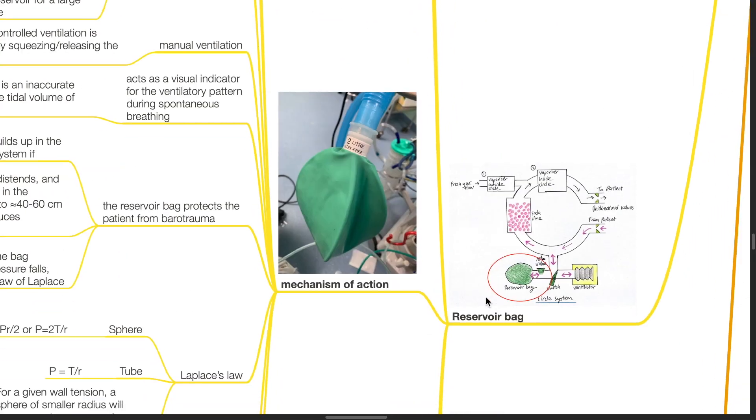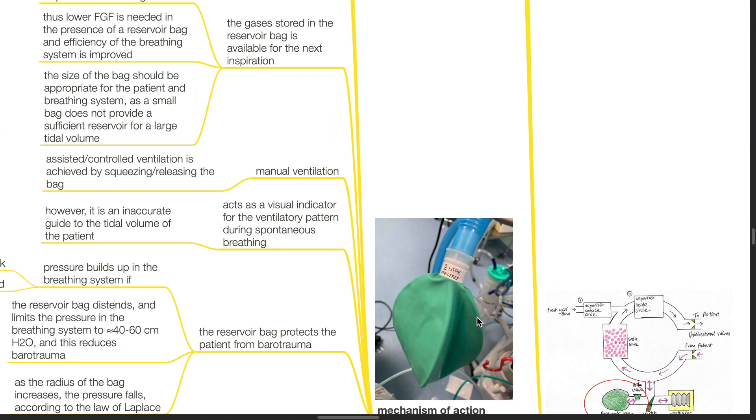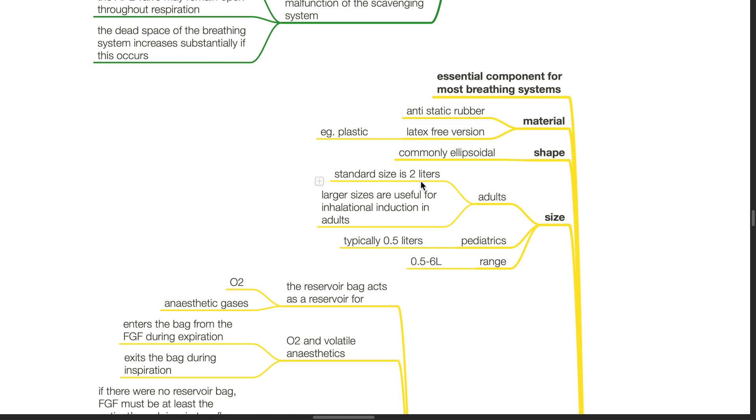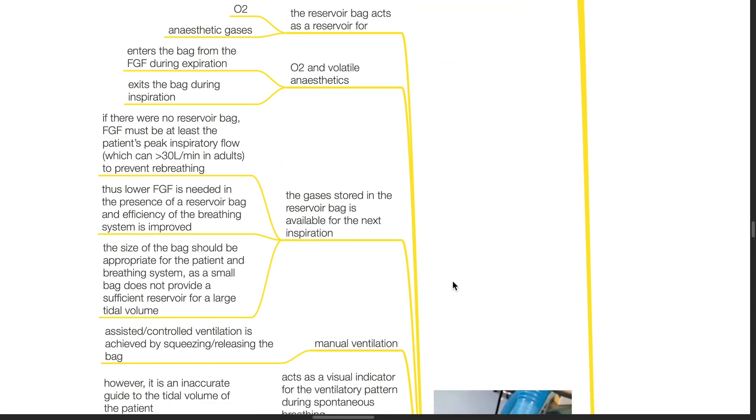Next we move on to the reservoir bag. It is an essential component for most breathing systems. It is made of anti-static rubber or plastic which is latex-free. It is commonly ellipsoidal in shape. Standard adult size is 2 liters. Larger sizes are useful for inhalational induction in adults. Pediatric size is typically 0.5 liters. The range of sizes is 0.5 to 6 liters.